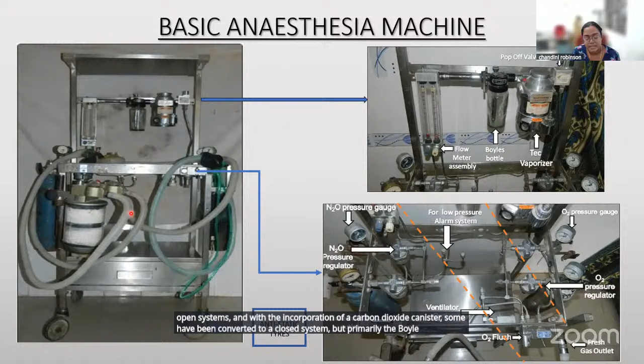The pressure regulators ensure that the high pressures of oxygen and nitrous oxide are decreased to an intermediate pressure. From there, the gases will travel through the flow meter assembly, the vaporizer, and through a common gas outlet. There is an oxygen flush system, which will allow for higher volumes of oxygen to be delivered in case of emergency. The older anesthesia machines were not fitted with a ventilator, so they were primarily open systems. With the incorporation of a carbon dioxide canister, some have been converted to a closed system, but primarily the Boyle's machine is meant for the open circuit system.